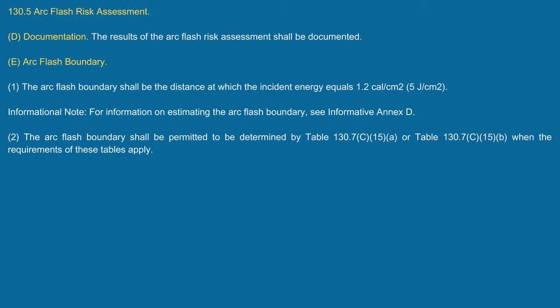If you look at the arc flash boundary here, it says the arc flash boundary shall be the distance at which the incident energy equals 1.2 cal/cm². Anything over that is going to change everything, but up to 1.2 cal, that is considered a curable burn. Okay? If I calculate that, I'd probably put on maybe 3 cal just to make sure I didn't even get a second degree burn. But that's based on a second degree burn. And if you look at the informational note, it tells you when you're determining that arc flash boundary, which annex do I go to? Looky there, Annex D. And that's why I said you pick up 3.32 and 3.33, okay?